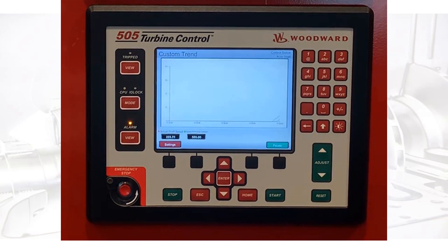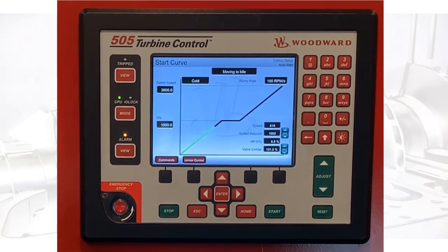All commands via communication links, whether it's the front panel graphical user interface, remote view, or Modbus, can be issued to either the syscon or the backup unit. The operating system will ensure that the commands are processed by the syscon unit and that the control state is passed to the backup unit to keep it in sync and available for a transfer.